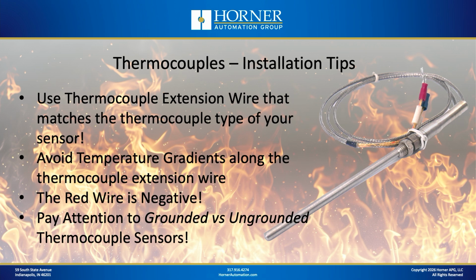Another thing to keep in mind is you want to avoid, if possible, any large temperature gradients along the wiring from the probe back to the PLC. That will introduce some extra error. So if you can just avoid running that extension wire through some areas that have extremely high temperature gradients, then you'll be fine there. Again, I want to stress the red wire is negative.